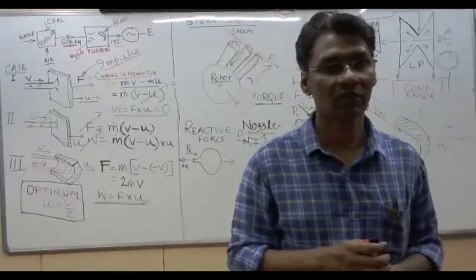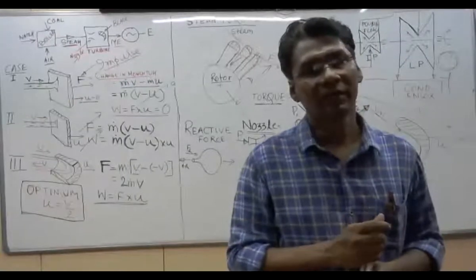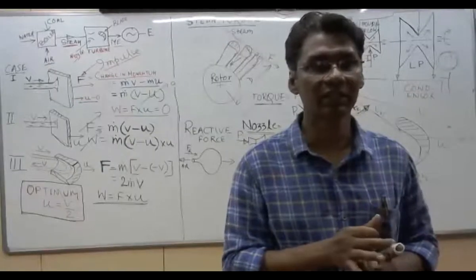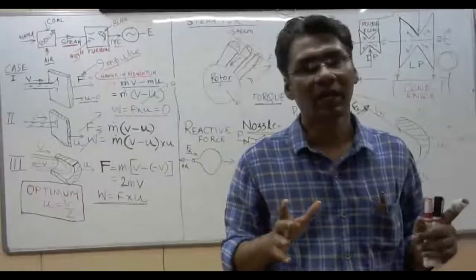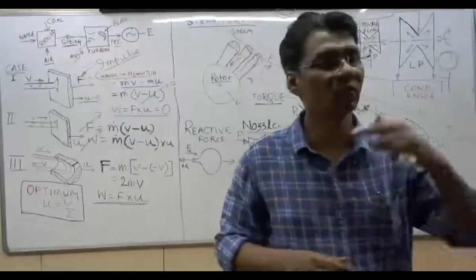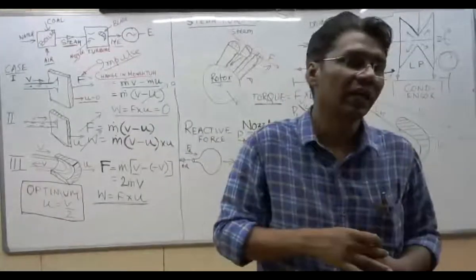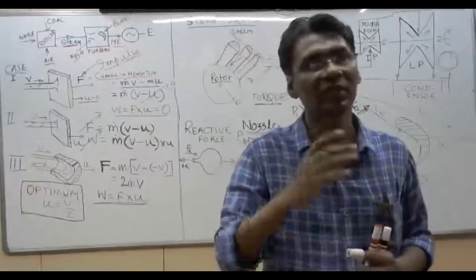Why are these control valves controlled, and using which type of control system? The turbine is controlled by oil pressure through a governing system, the turbine governing system. It depends upon the steam amount, frequency, and a lot of input parameters. These are processed by a microprocessor, and a signal is generated to produce some oil pressure. That oil pressure controls the control valve. This is in short. Actually, the governing system is not so easy, and by the governing system we control the turbine speed.